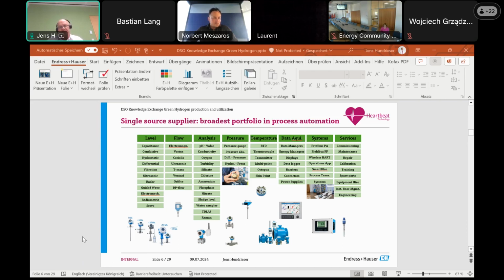This we have for all new instruments, so you have it permanently checked. I compare it with a car: when you go check your car if it's okay, we have a verification, and this verification is not a calibration. The device stays in the process, and it's a check to a high percentage. For a flow device, for example, 95% of all sensors and electronics can be checked.